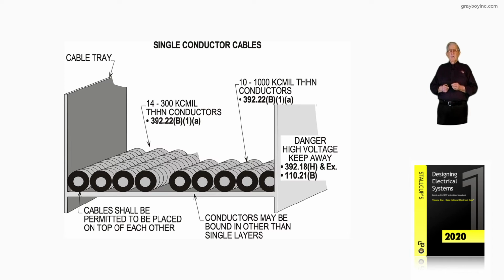392.22(B)(1)(a). So, in dealing with these conductors that we see to the right, they may be bound in other than single layers when we go through the section, again, so the current will divide more evenly on L1, L2, and L3 and neutral, if that be the case. And then if you have high voltage, over 1,000 volts, then we just call your attention and say, you have to identify that on the tray.